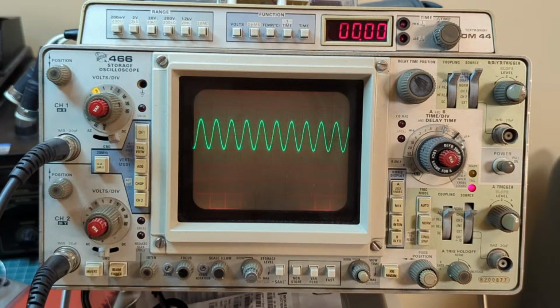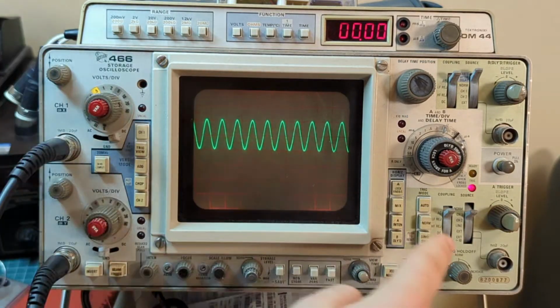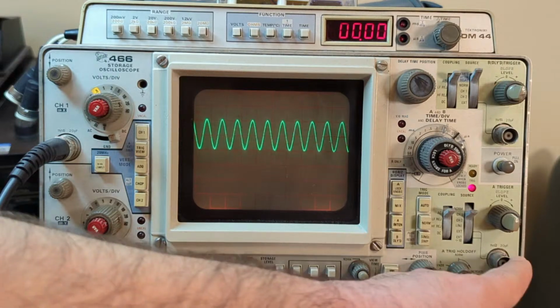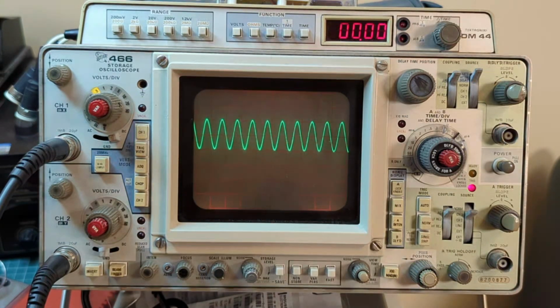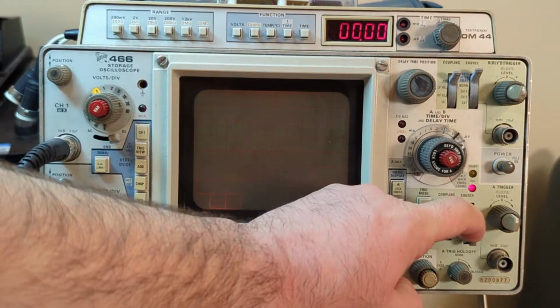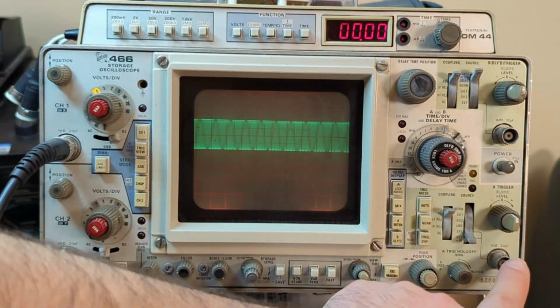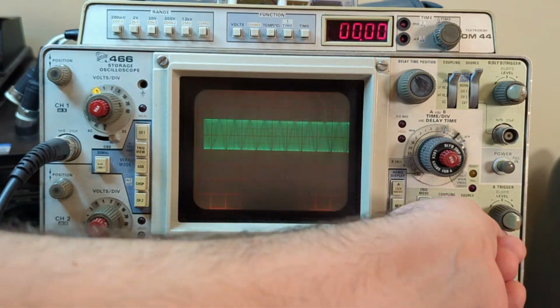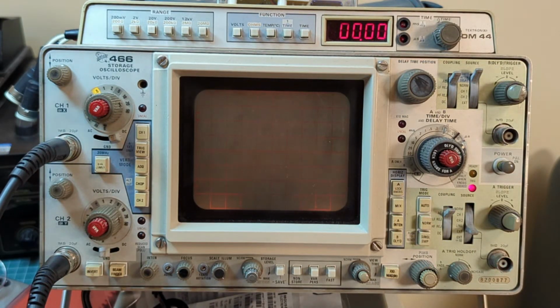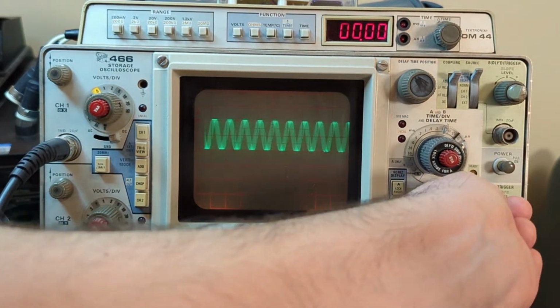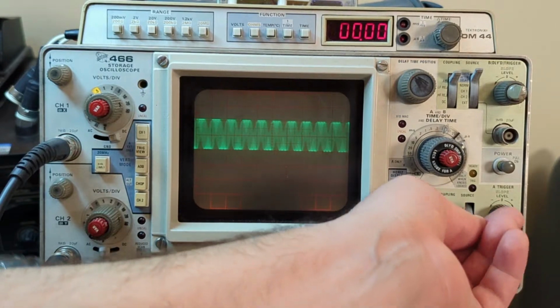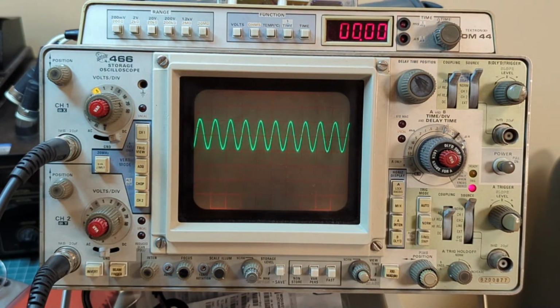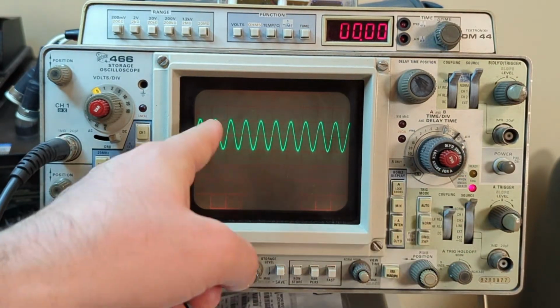So depending on what you're trying to get, you can adjust the trigger polarity. As I said, you can adjust the trigger source, and most scopes can even be triggered externally by some other signal, and you can select this. You can select external triggering, and then it triggers to whatever you feed into this BNC connector. You can also trigger it onto the line frequency, which is useful for working with line frequency circuits, of course. And you also have a normal mode, which I forgot how it works, but it usually triggers to whatever you have on the display.